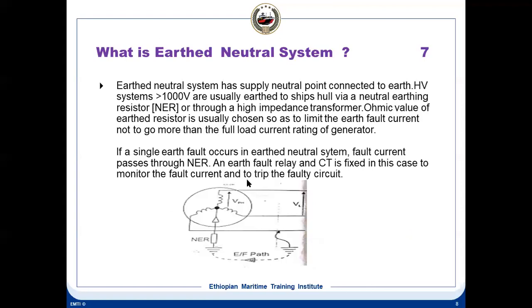An earthed neutral system has its neutral point connected to earth. Especially high voltage systems, which are more than 1000 volt, are usually earthed to the ship's hull by a neutral earthing resistor. You can see it's called the neutral earthing resistor, NER.